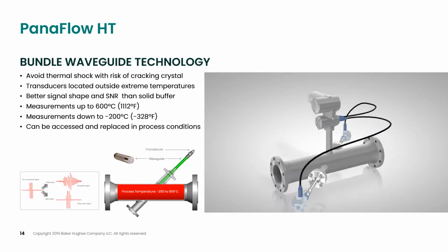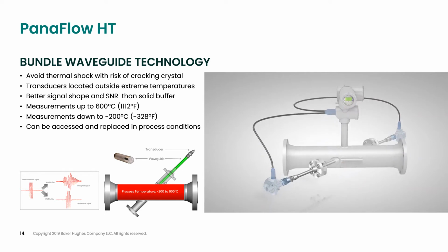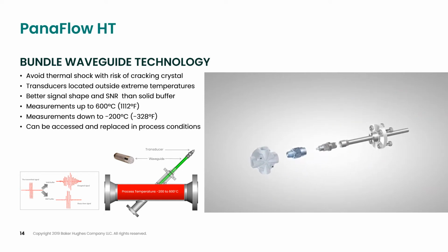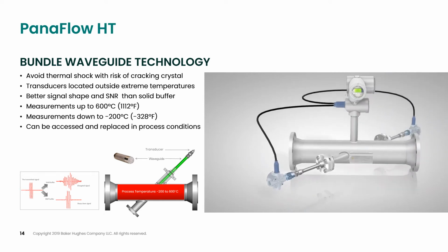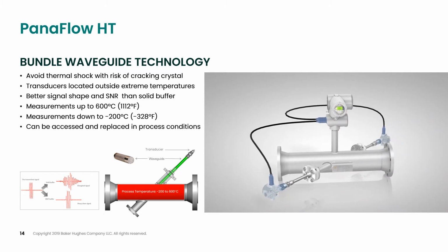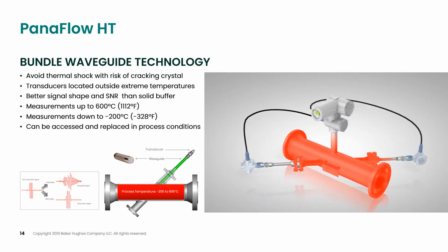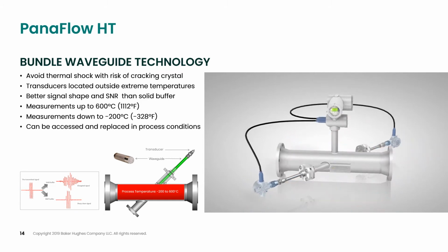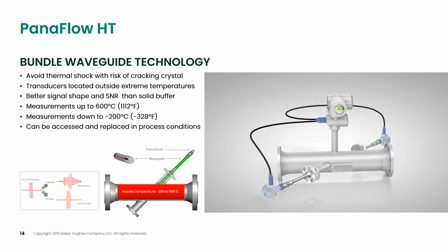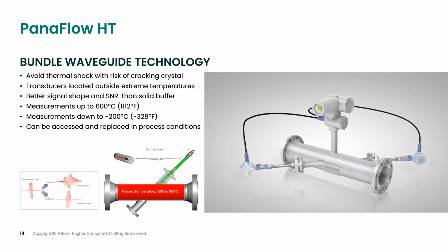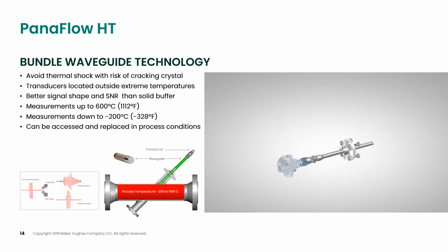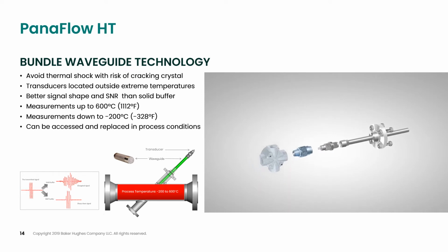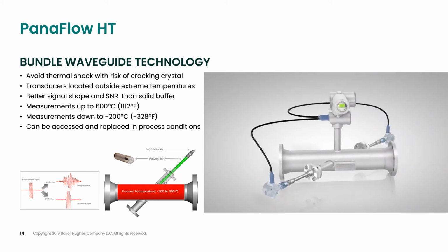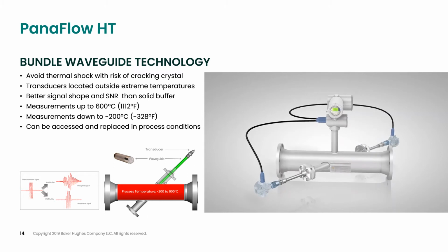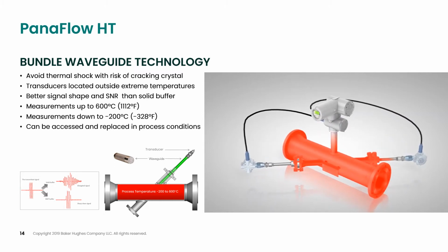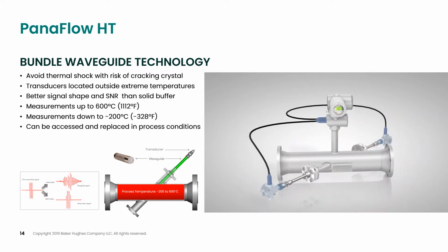PanaFlow HT utilizes our bundled wave technology. The concern with extreme temperature applications is that the transducer will be damaged by the thermal shock with the risk of cracking the crystal and permanently damaging the transducer. To resolve this issue, the transducers are located away from the extreme temperature with a bundled wave buffer. The bundled wave buffer provides a waveguide for the ultrasonic signal and produces a significantly better signal shape than a solid buffer. With this waveguide, we can go up to 600 degrees Celsius or over 1100 degrees Fahrenheit for almost any application in a refinery.